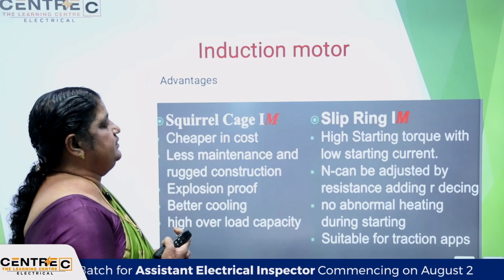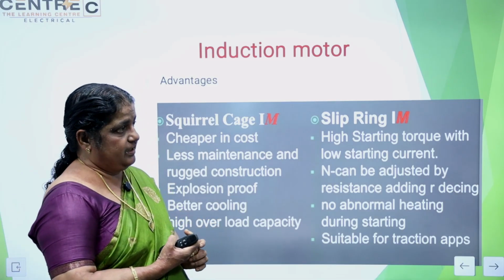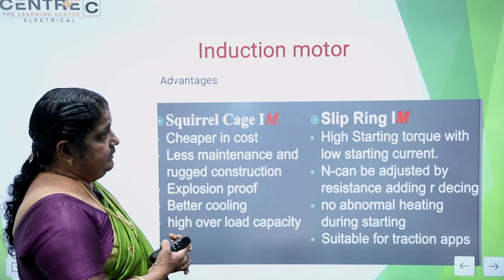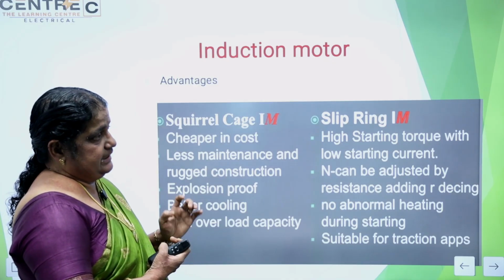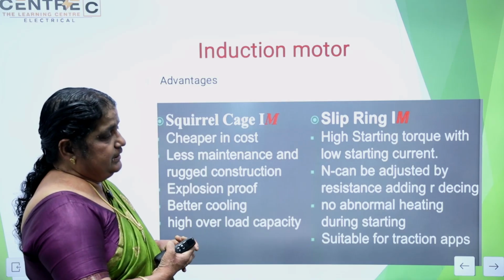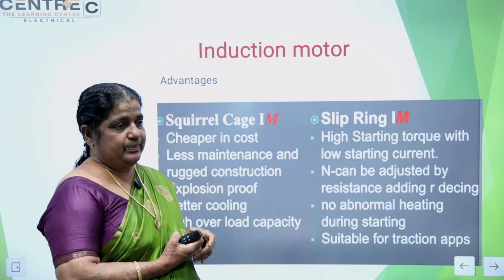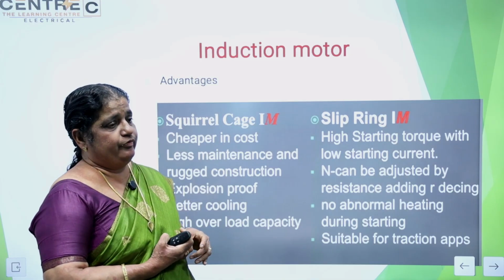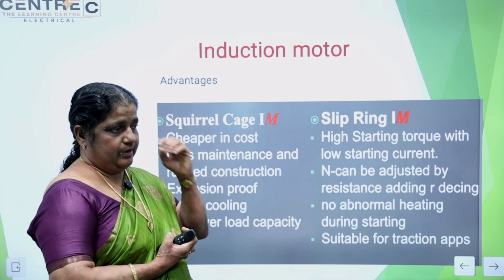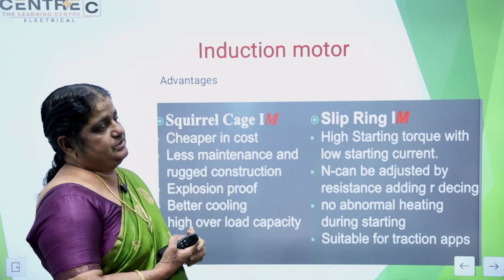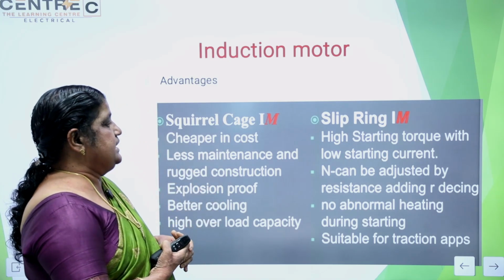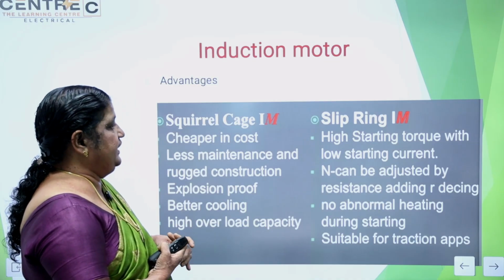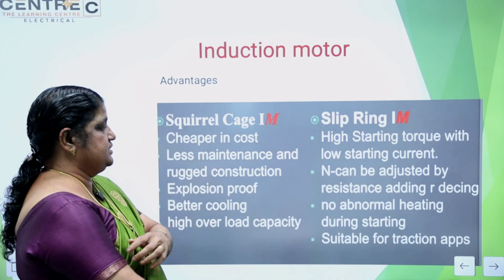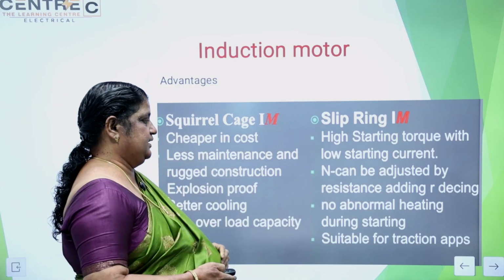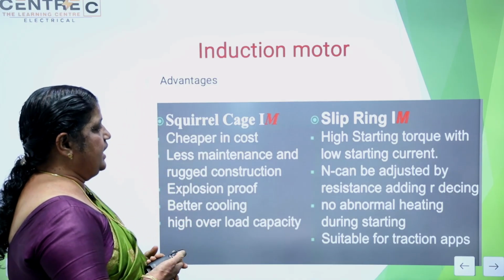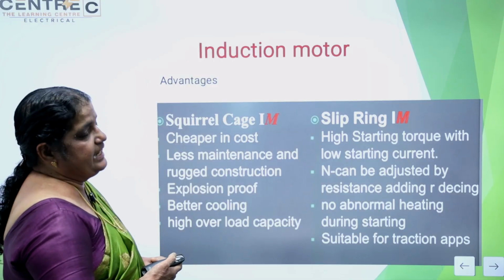One important thing is when the induction motor is starting. First of all, the back EMF is 0, and the full voltage is suddenly applied to the stator winding, so the current produced is very high. Mainly, say 1 ohm is the stator resistance. We can apply 415 volts, then 415 by 1 gives 415 amperes. So this will be very high. So starters are used to start the induction motor. Mainly the auto transformer starter and star delta starter and other different starters can be used. DOL starter, direct online starter: up to 5 HP motors we can use a direct online starter.